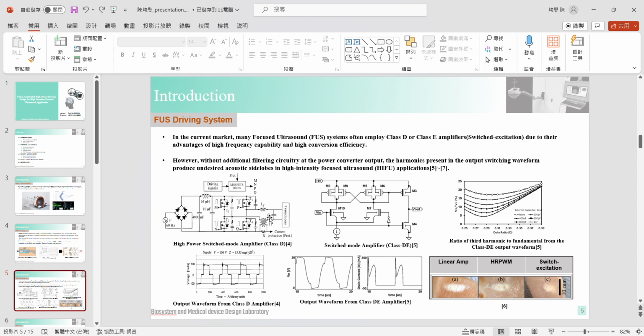This is the Class D driving circuit, and this is Class DE. Their output waveforms look like this and like this. We can see that the ratio of their third harmonic to the fundamental in the Class DE output waveform is about 20% to as low as 5%. And if we do not do any adjustment, the switched excitation results will be very different from the linear amplifier, like this and this.